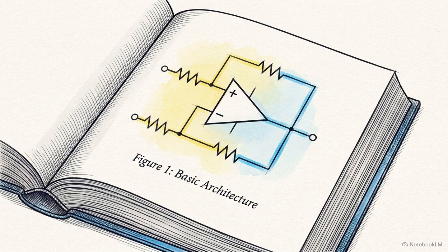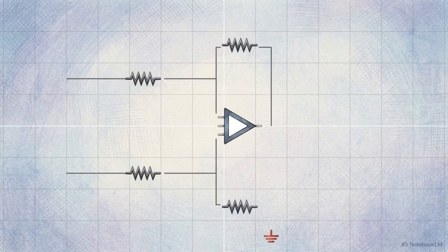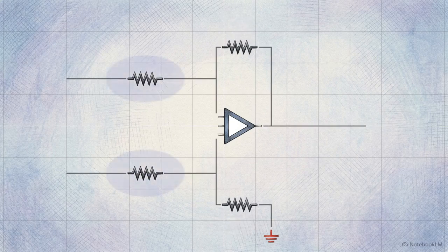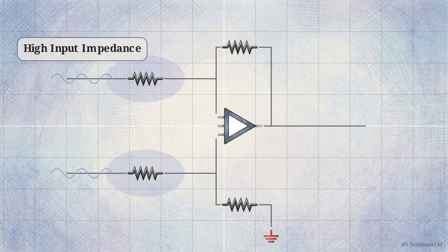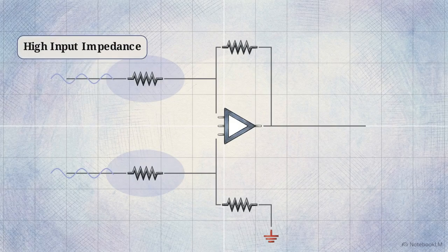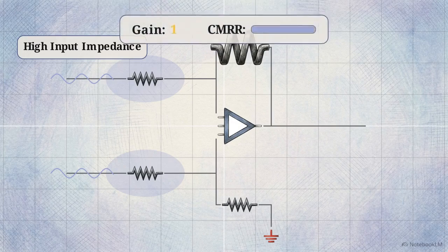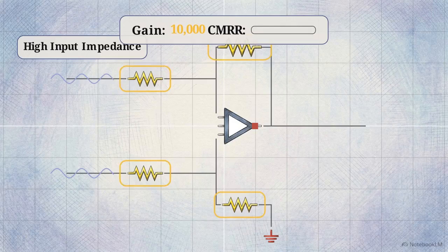The most basic approach to this problem is a standard single op-amp differential amplifier. To measure a fragile source signal without drawing current, the circuit requires extremely high input impedance at these two highlighted input resistors. Simultaneously, achieving high differential gain requires an extreme ratio between the feedback and input resistors. This creates a direct conflict: pushing for high impedance and high gain simultaneously degrades the common mode rejection ratio.